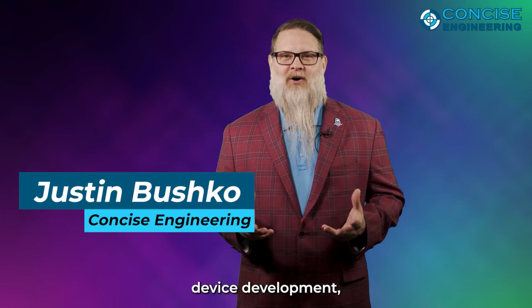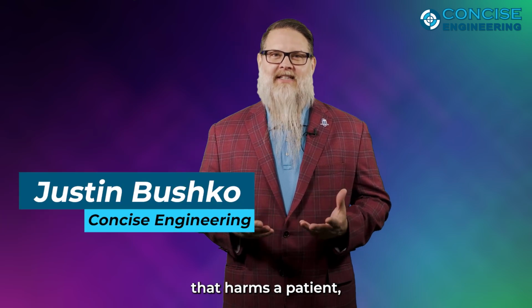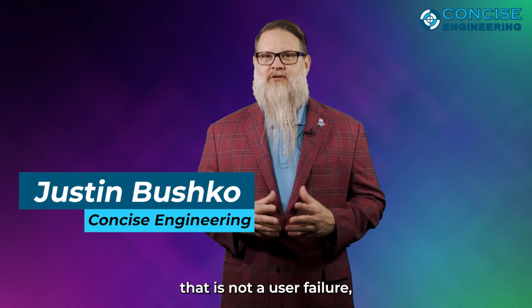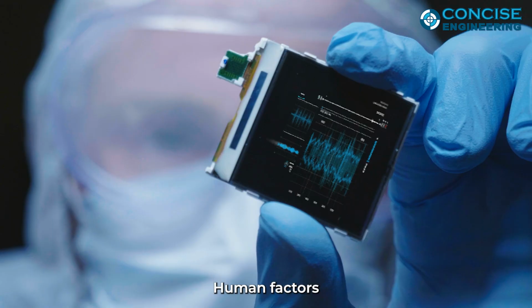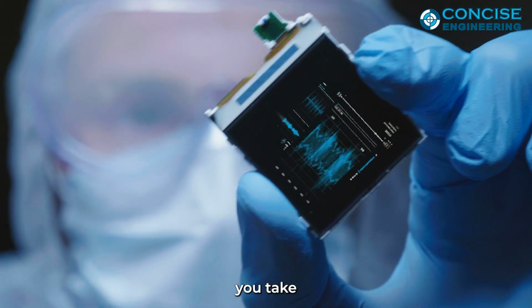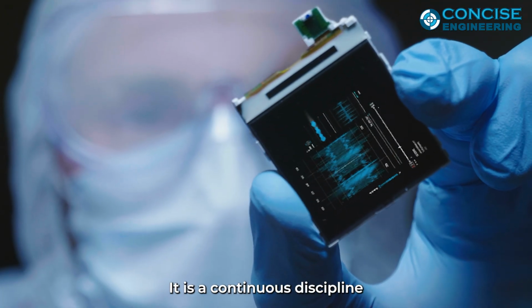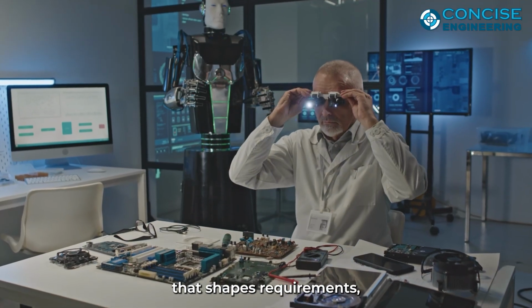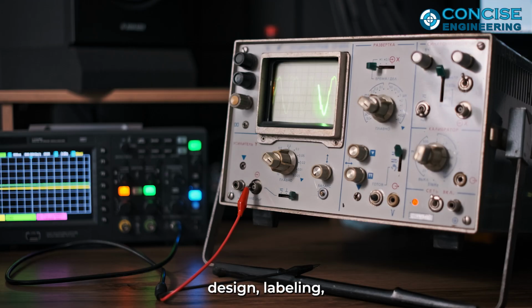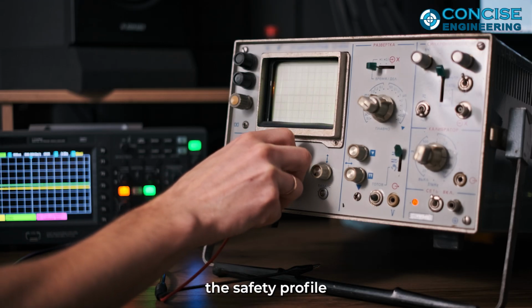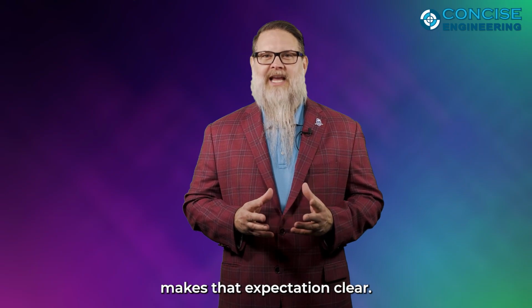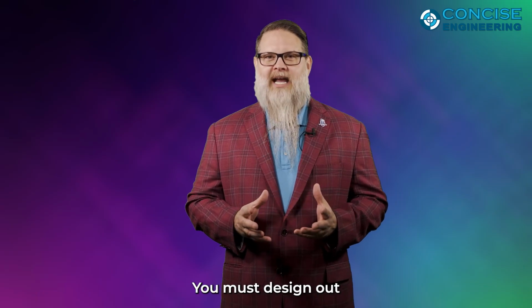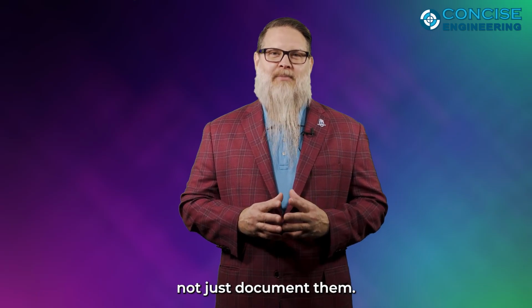In medical device development, if a user can make a mistake that harms a patient, that is not a user failure, it is a design failure. Human factors engineering is not a test you take at the end of the project. It is a continuous discipline that shapes requirements, architecture, interface design, labeling, and ultimately the safety profile of the device. IEC 62366 makes that expectation clear. You must design out use errors, not just document them.